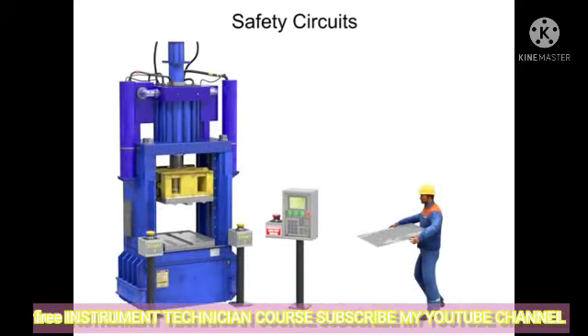While two-hand controls wired in series is ideal for machines with two operators, it becomes unsafe when only one operator is present. Although two buttons are still required, it becomes much easier for a single operator to tie or weigh down one button, allowing unsafe operation.